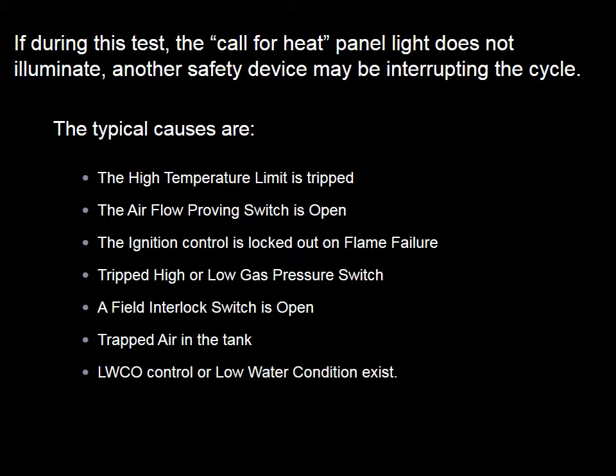If during this test the call for heat panel light does not illuminate, another safety device may be tripped and interrupting the cycle. The typical causes are: the high temperature limit is tripped, the airflow proving switch is open, the ignition control is locked out on flame failure, the high or low gas pressure switch may be tripped, a field interlock switch is open, there is trapped air in the tank, or a low water control or low water condition exists. Check the troubleshooting section of the maintenance manual for corrective action.